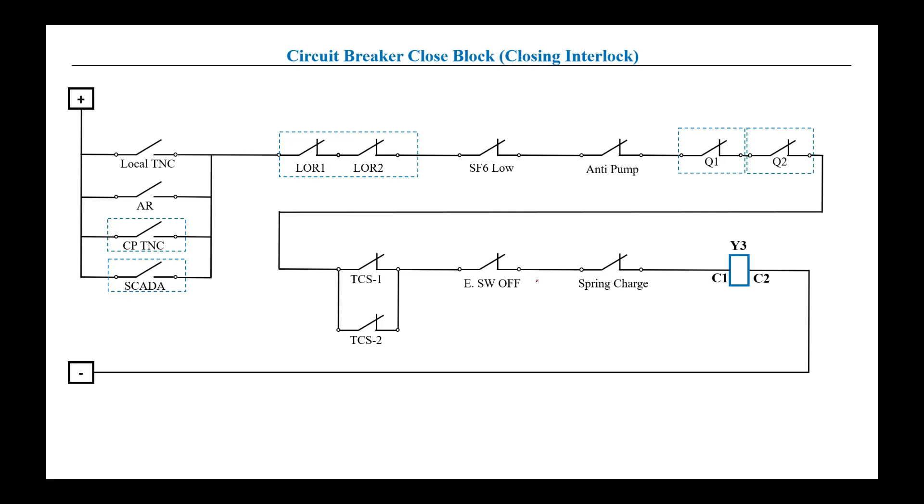If any one of these interlocks is open, the closing coil will not be energized, the circuit breaker will not close, and the protection, maintenance, or control team has to take care of this problem. There are four ways to close the circuit breaker: one from the local TNC switch at the switchgear, second through AR closure, third from the control panel, and fourth from the SCADA. Whenever any one of these four options is activated, positive will extend from the initial stage up to the first interlock.